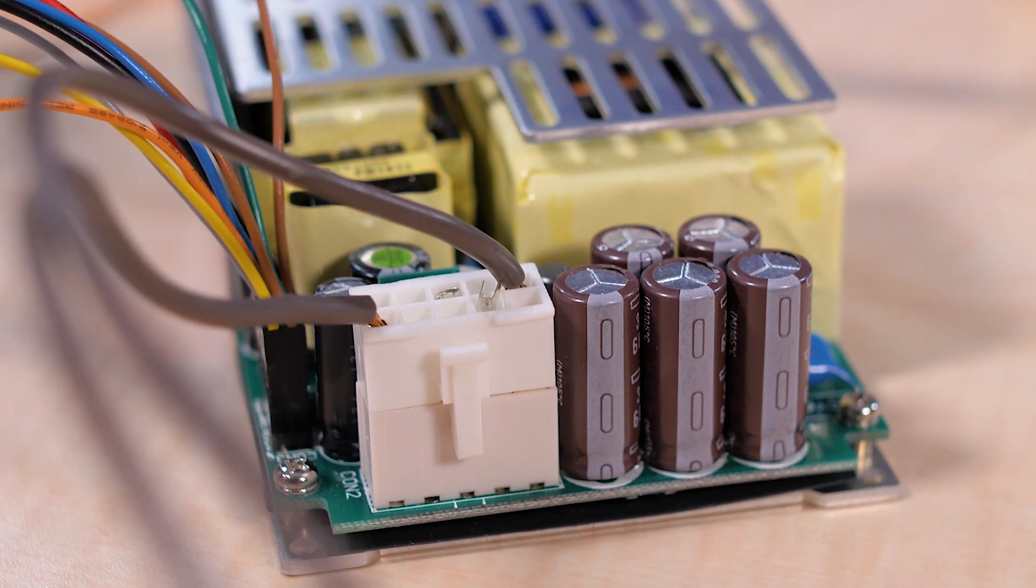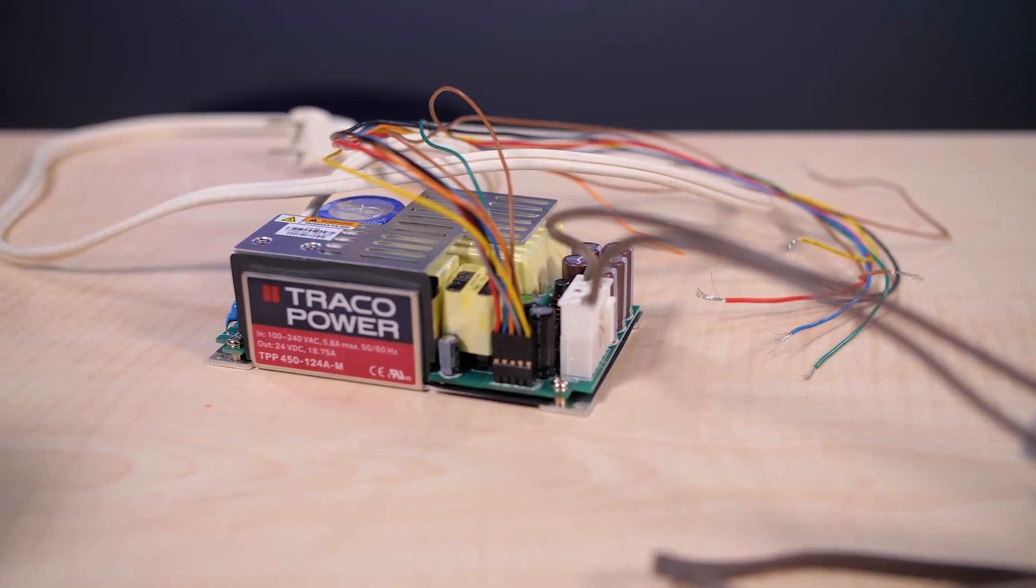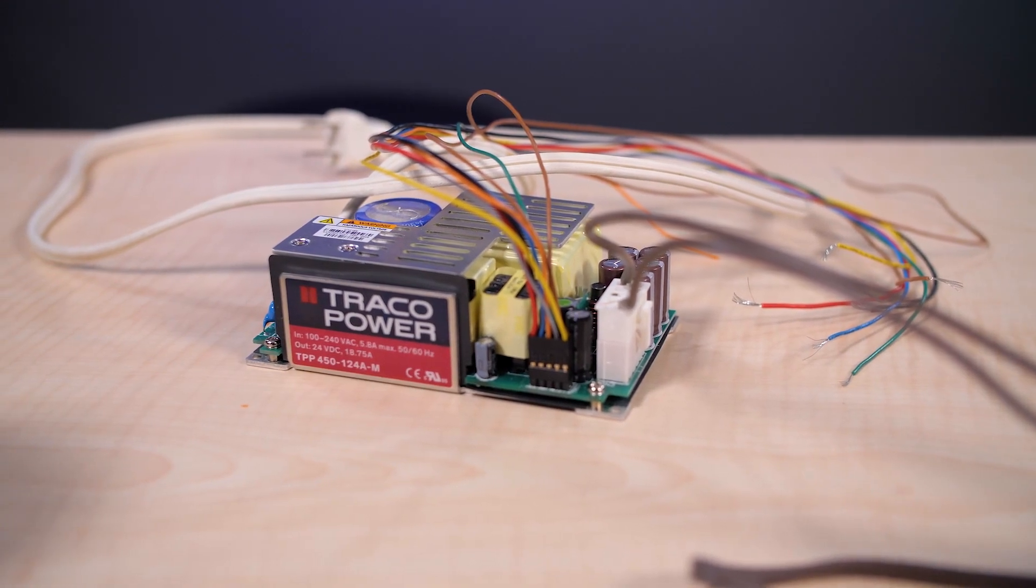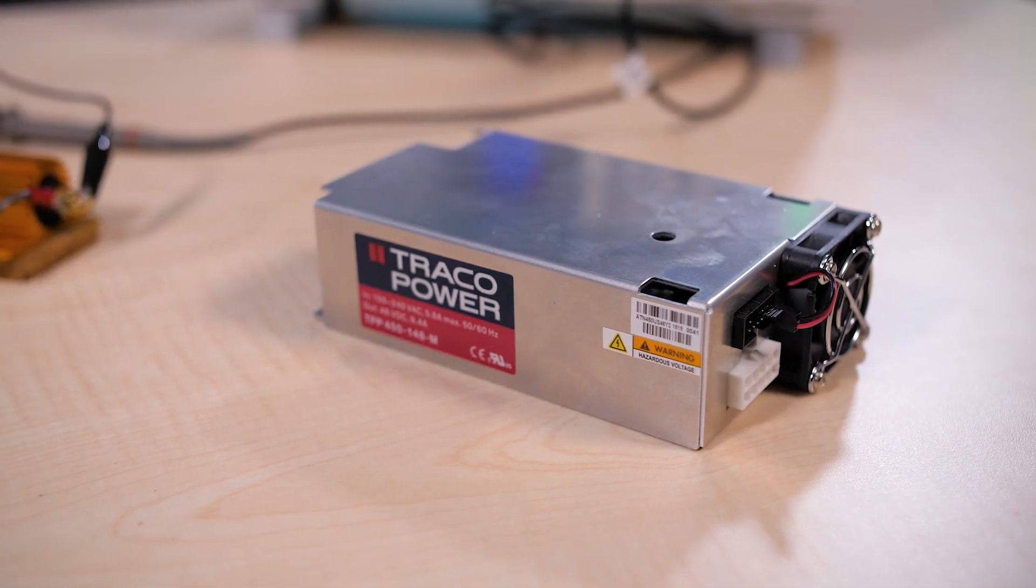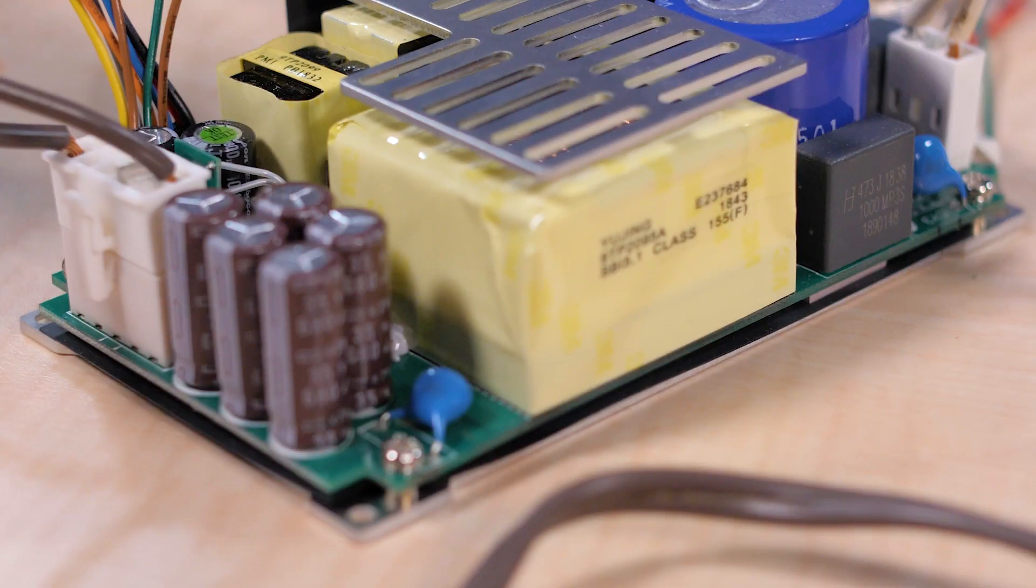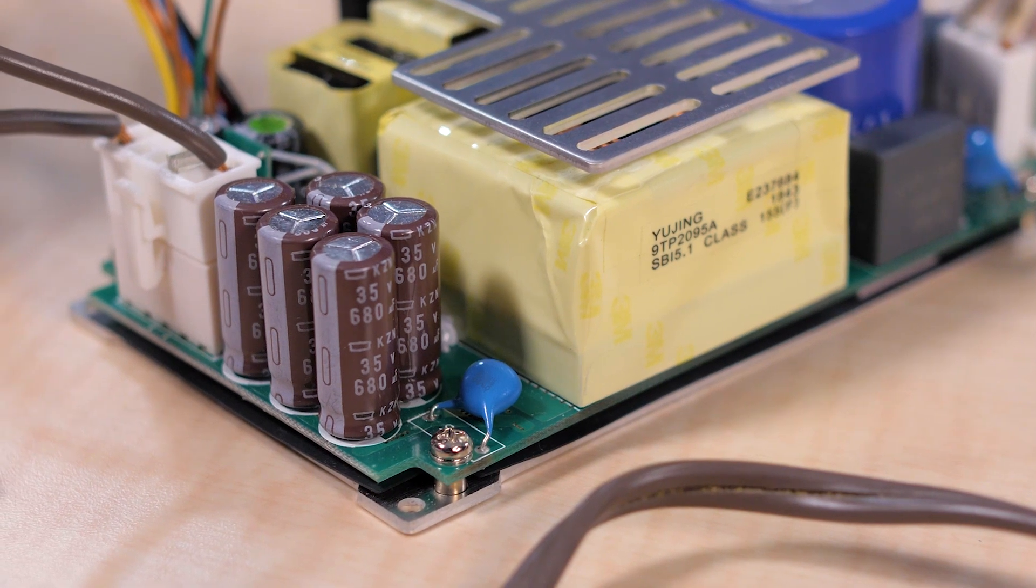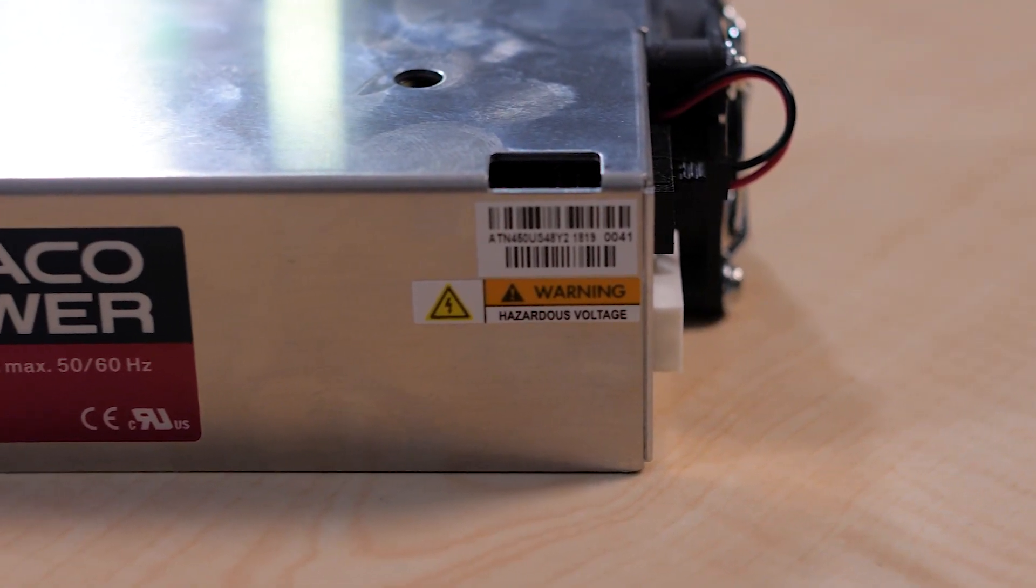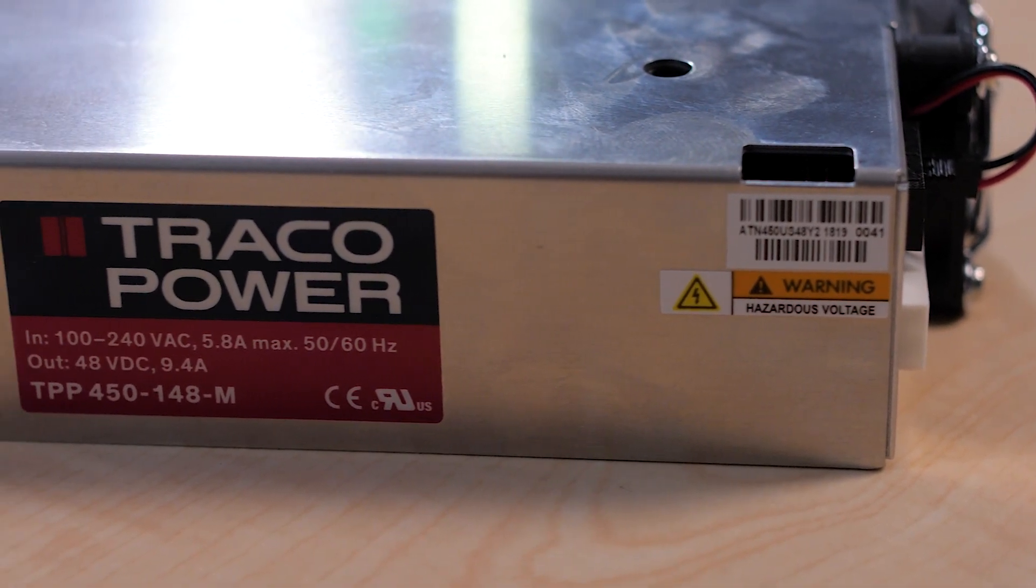These supplies have medical certifications along with IEC UL 62368-1 approval for more general purpose uses. They all limit earth leakage current to below 100 microamps, which lets them handle body floating applications. Other operational parameters that come out of their medical certification include operation to at least an altitude of 5000 meters and meeting a workmanship standard called IPC-A-610 Class 3, which is more stringent than the default standard.